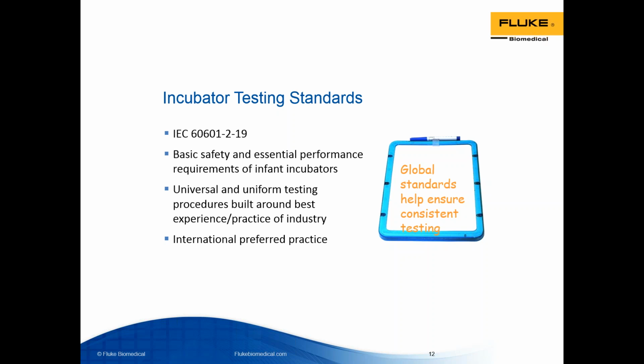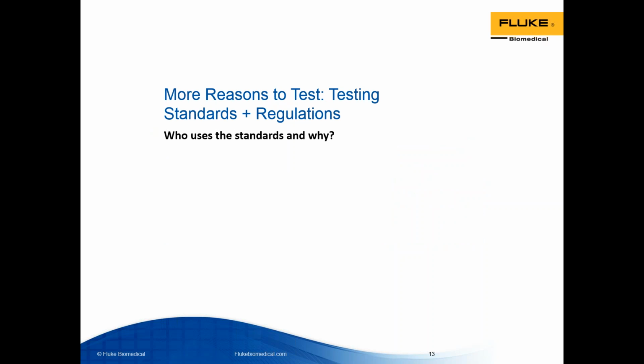So for this reason, most of the local, national standards, and what I mean by local, national is by country standards, have been harmonized to the IEC standards, which are recognized as the international preferred practice. The IEC 60601-2-19 standard recommends the basic safety and essential performance requirements specifically for infant incubator testing. As it turns out, testing standards and regulations go hand in hand, especially when we consider more reasons as to why it's important to test and verify the performance of incubators.